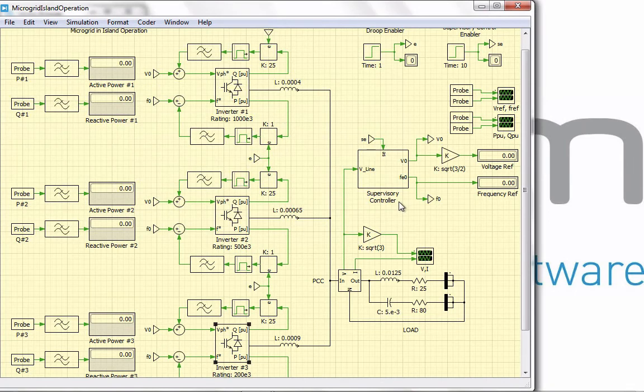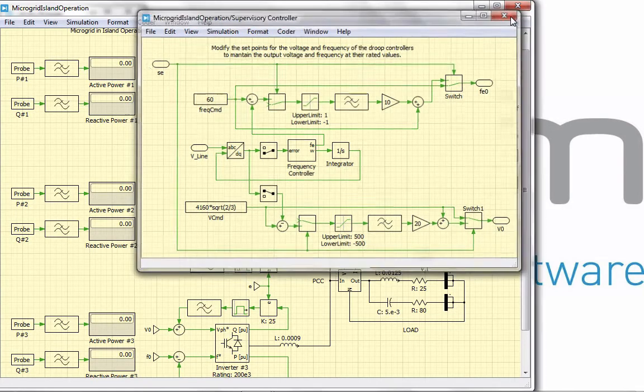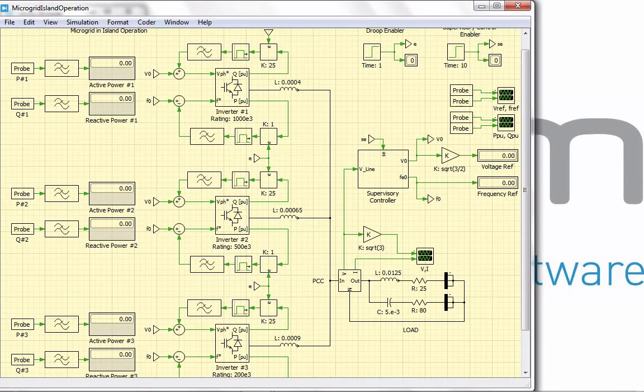Supervisory controller is used to dynamically determine frequency and voltage references. This control changes the open loop reference very slowly such that at point of common coupling or PCC, the voltage and frequency are maintained at close to reference values. The droop control for a standalone microgrid is based on mimicking the operation of a synchronous generator.